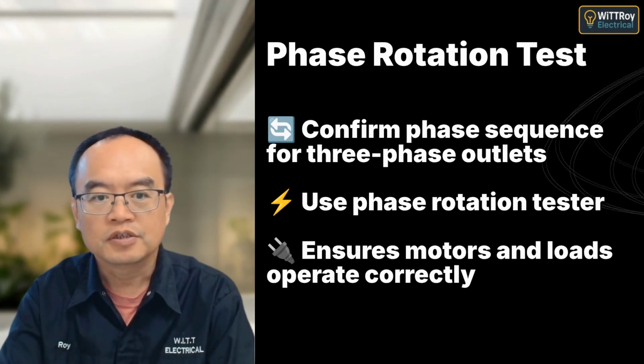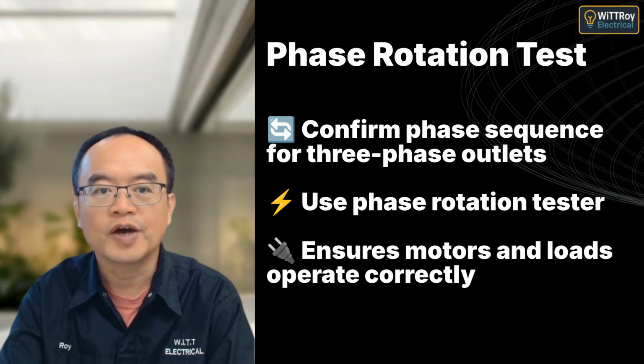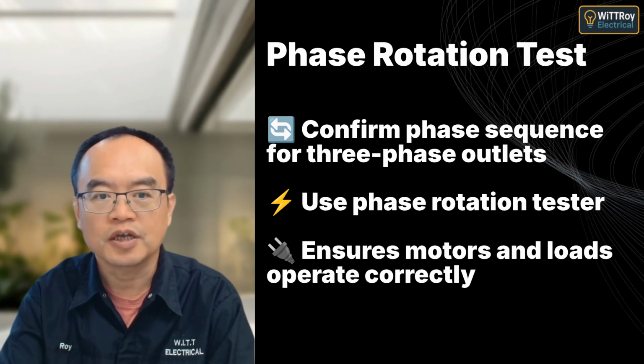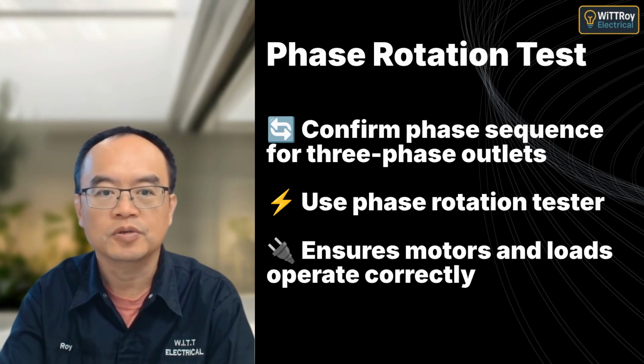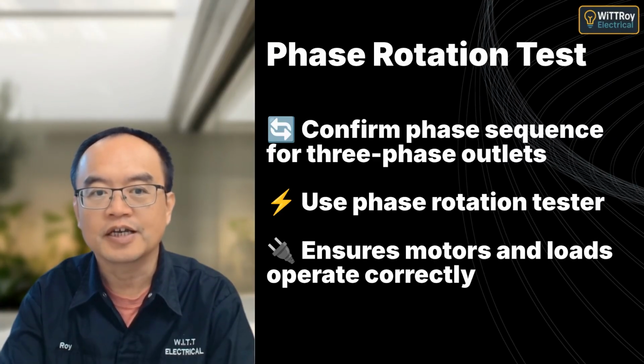In 3-phase installations, use a phase rotation tester to verify correct sequence. Incorrect phase order can cause motors to run in reverse or not at all. Always test outlets before energizing connected equipment.